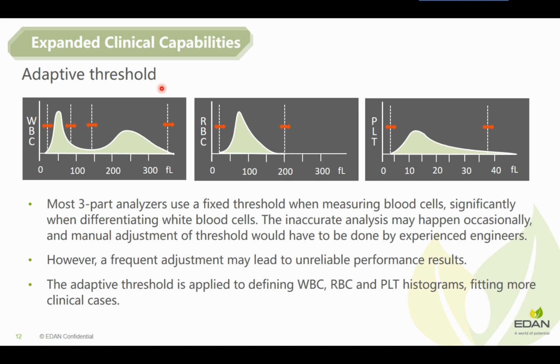The main drawback of the fixed threshold is that the accuracy of white blood cell differentiation will be diminished significantly, particularly on abnormal samples. I guess you must have experienced adjusting the threshold manually. But after the adjustment, you may still find some inaccurate 3-part results. In the end, you are stuck in a vicious circle between unreliable results and frequent adjustment. Therefore, using the adaptive threshold is one of the ultimate solutions to ensure the performance. That's where we improve on the H30 Pro.